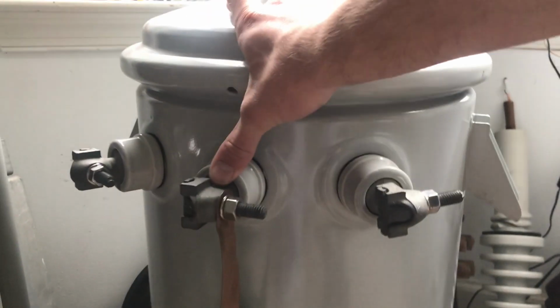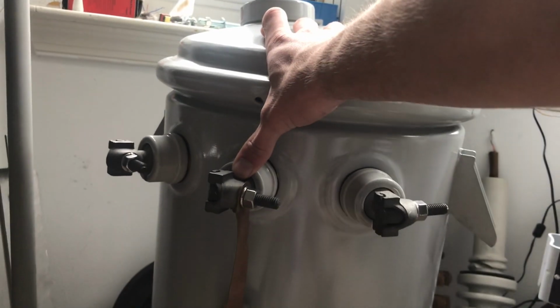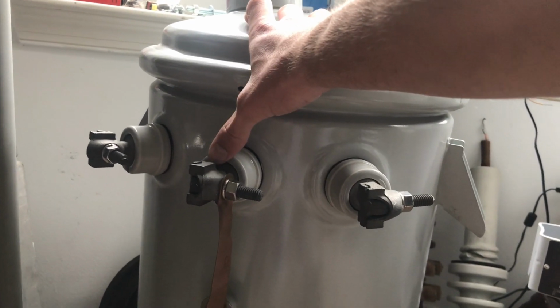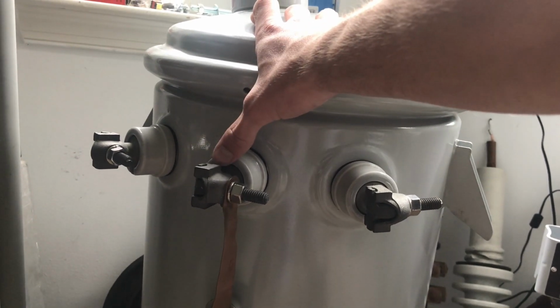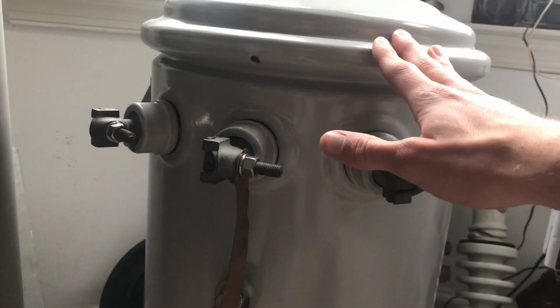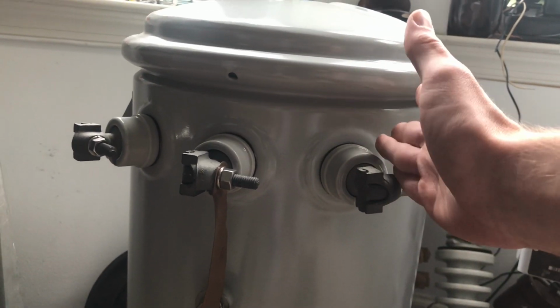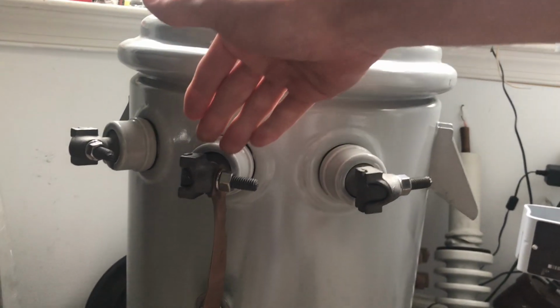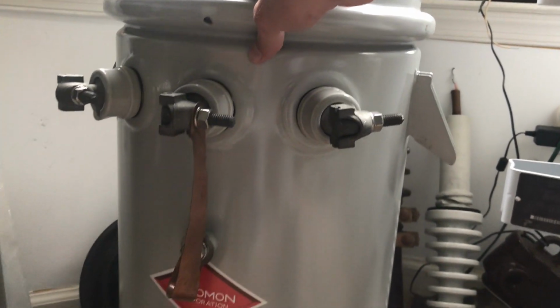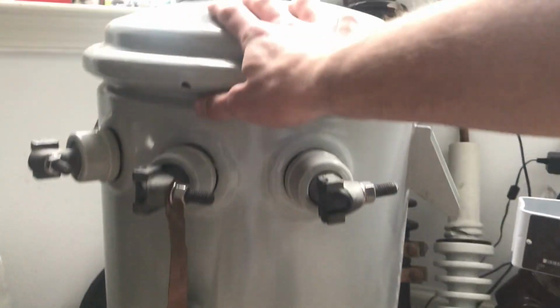On transformers larger than 100 kVA, so usually 167 kVA and above, there'll be a bushing here and then 2 bushings here, and the other one on the end. And a utility will usually series or parallel them depending on what voltage they want out of the transformer.